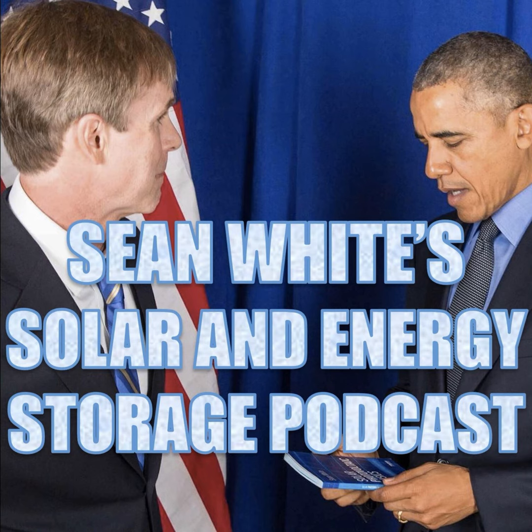705.11 is called supply side source connections, and 705.12 is called load side source connections. So we have supply side and load side. And this is all relative to which side of the main service disconnect you're talking about. If you are on the supply side, that's like the utility side of the main breaker. That would be called a supply side connection. A lot of people call it a line side tap when you're making a connection there.